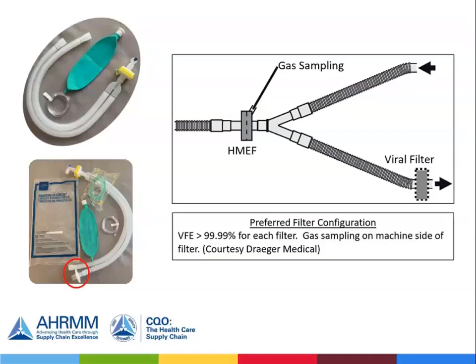And you can see in the picture to the left, we have an initial configuration of a circuit with our vendor that had a HEPA filter, the yellow filter that you see at the Y, but we needed an additional filter. And so in working with our vendor, we were able to source and create a new circuit design which complied with this recommended configuration, in which there's a high efficiency viral bacterial filter placed in the expiratory limb of the circuit, and they would be provided to us in that configuration without us having to search, rather, I'm afraid, fruitlessly, for additional filters to protect our anesthesia machines. And with that, I will turn it over to our supply chain folks.